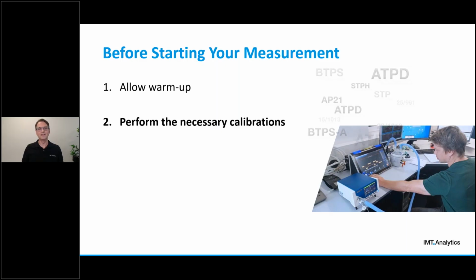The second thing to consider before you start measuring is to perform the necessary calibrations on your gas flow analyzer. So depending on the application and the device you use, the following calibrations should be performed. First and most important, a zero offset calibration. This applies for any measurement task and should always be done. The purpose here is to avoid that we take measurements with sensors that have drifted. That's why it's crucial to perform the zero offset calibration after the warm-up of your device. So we'll zero out any drift that happens during the warm-up of the devices.